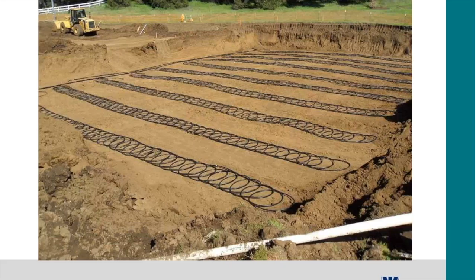For systems installed in Hawaii, where there's no winter, or in the north like Canada in the summer, can geothermal be installed? They do all kinds of geothermal projects in Canada. The difference there is they're typically looking at systems that are heating dominated instead of cooling dominated like here. If you weren't able to put enough ground loop in the earth, you'd look at a hybrid system using a boiler or solar as backup. In Hawaii, that would be a bit more challenging - you'd probably want to put all your heat rejection from air conditioning into domestic hot water or something similar.